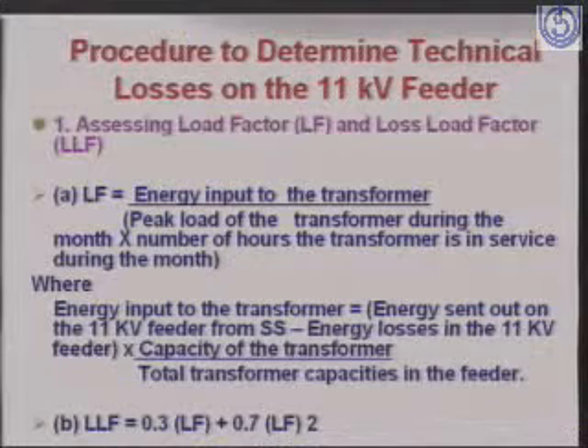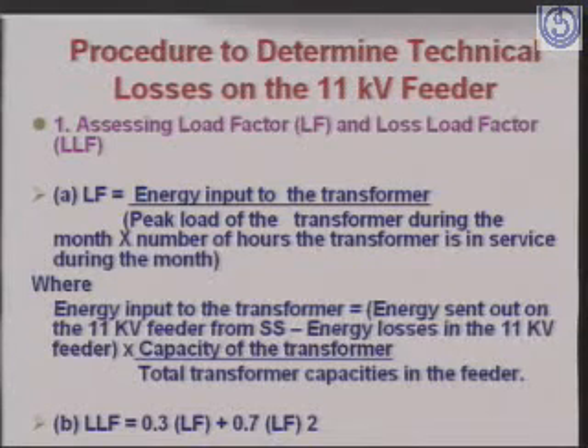Then the second concept is the loss load factor, which is basically 0.3 load factor plus 0.7 load factor squared. If you don't want to get into these details, then a very simple analysis is also available, which is normally used by many engineers in the industry. What they do is take the total energy consumed divided by the capacity of the transformer, square it, and multiply it by the copper loss of the transformer or the equipment. That's how they work out, not the total losses, but the copper losses of that particular equipment.